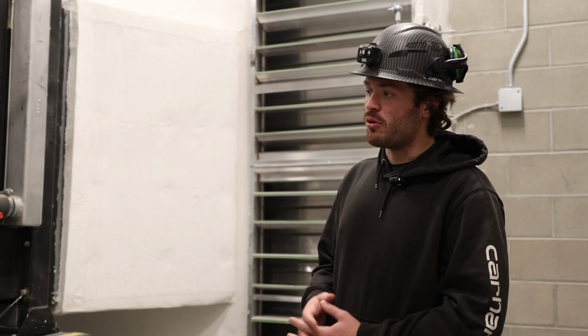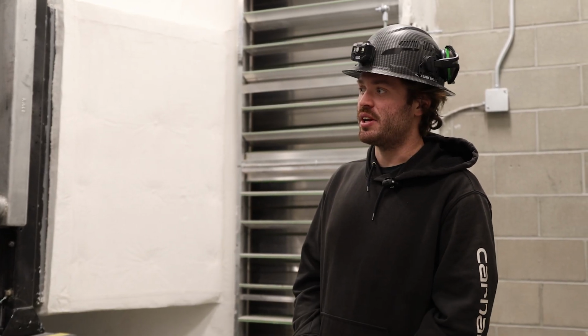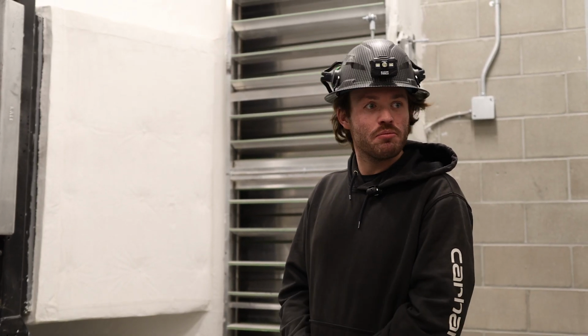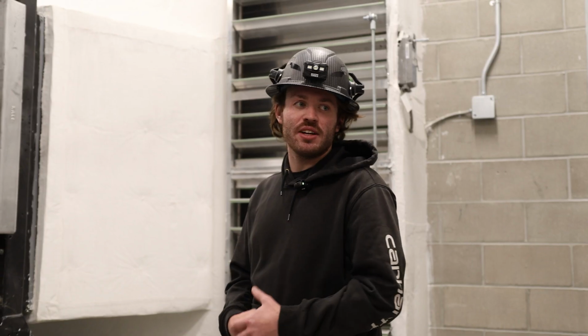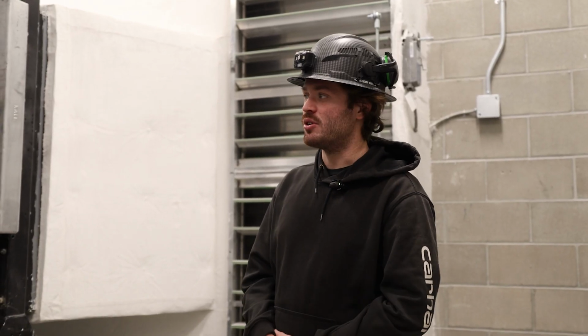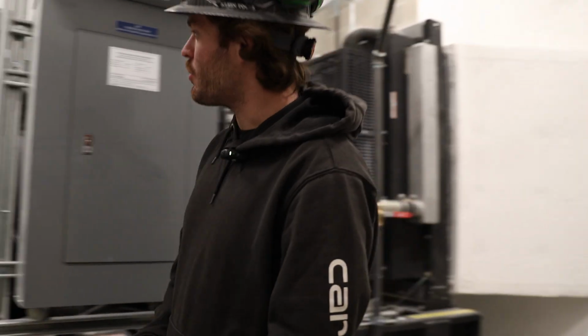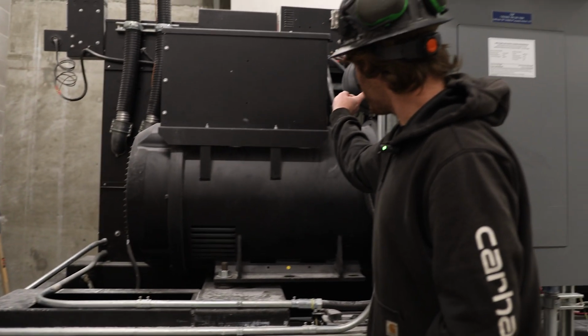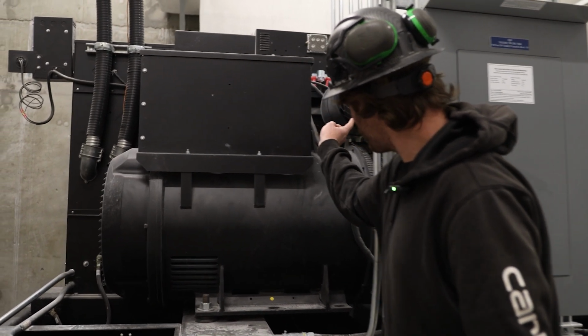It has a low level warning at 20%, which will send out an alarm letting you know that, hey, it needs fuel, and it'll continue to run. At 10%, it has a low fuel level shutdown, which will actually shut the unit down and stop the generator operation. That's done so we can simply refuel the unit versus having to refuel the unit and do a complete system prime of it. Towards the middle here, kind of hard to see because of our shore panel, is our air filter for the unit.